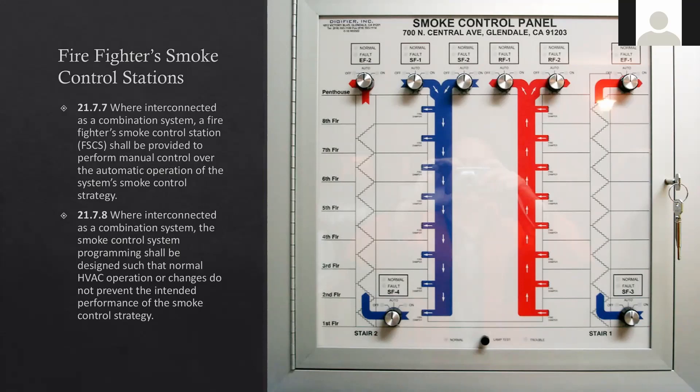Question from Ramsey: does the smoke control panel hook up the same way, or is there a specific way to interconnect it? Typically there'll be two relays — one shut-off relay and one command-on relay — and they'll still both be controlled by the SLC. You'll just have two relays for that air handler unit instead of one. Other than that, it's still pretty much the same as far as the physical install goes.